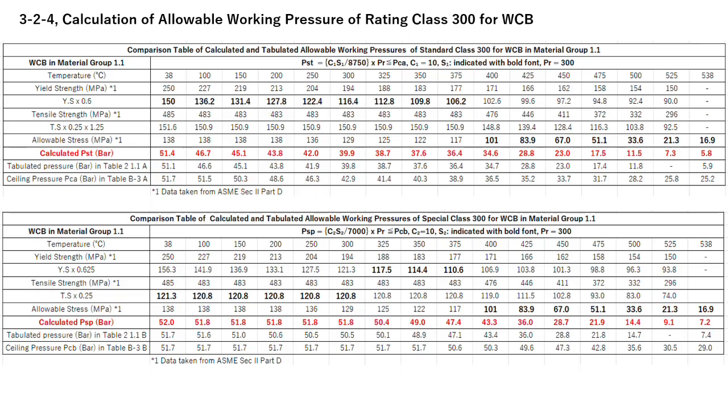So try to compare with the formal allowable working pressure. So tabulated pressure in table 2. This number is a formal working pressure. So compare with the calculated number. Almost same numbers are indicated like this. So that this calculation is, I think, okay.